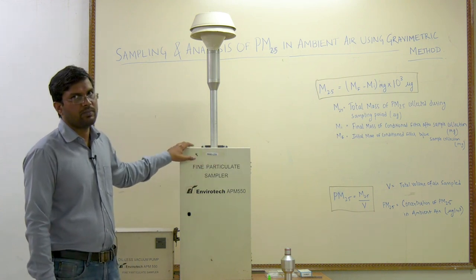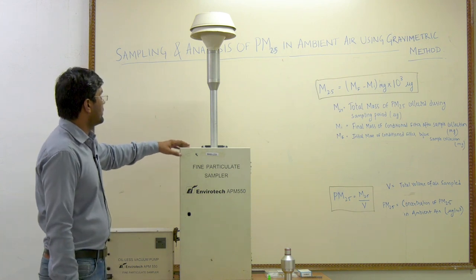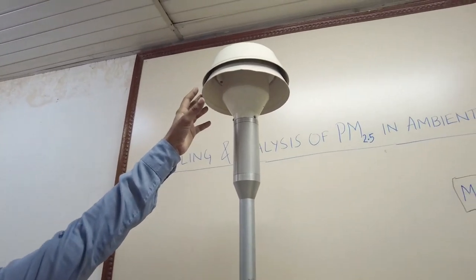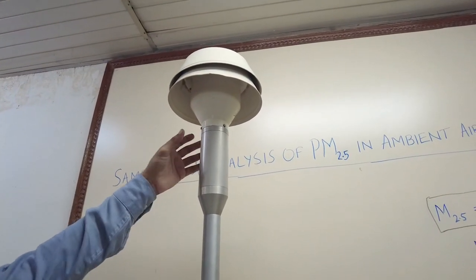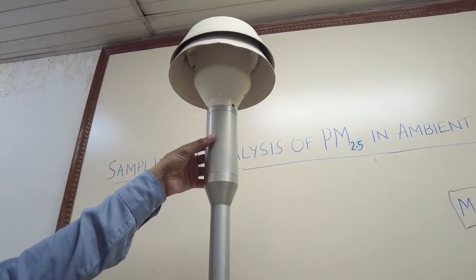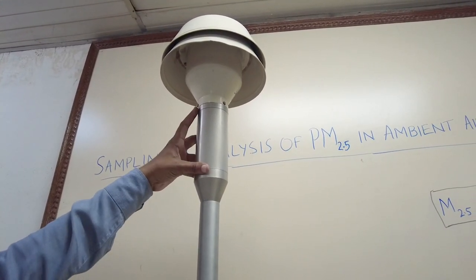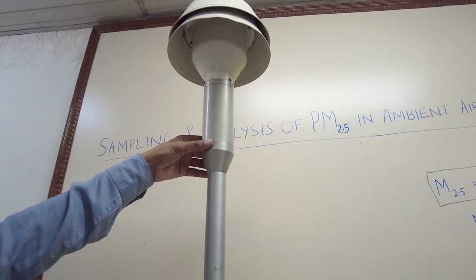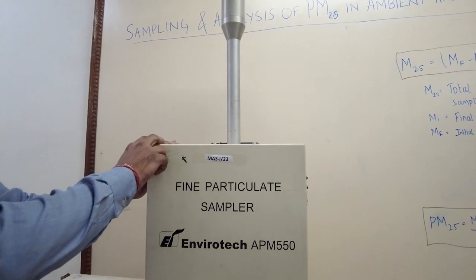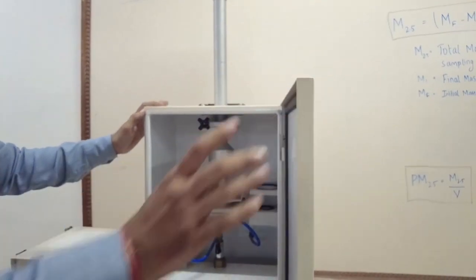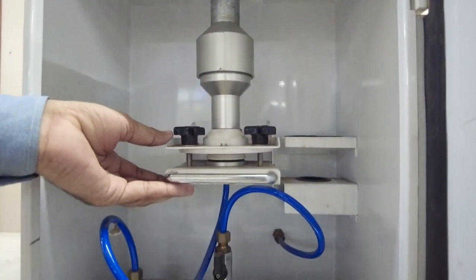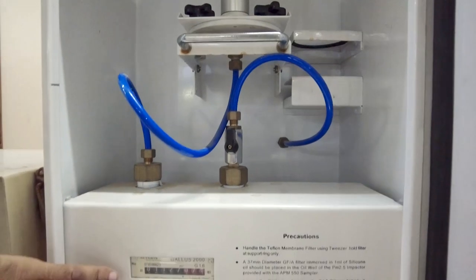I will explain the different components of the instrument. The upper part is called the inlet. After the inlet, this part is called the impactor — the PM 10 impactor tube — to segregate particles larger than 10 microns in size. Particles smaller than 10 microns will go through the air stream passing down through the down tube and into the housing of the APM 550 sampler. In the housing we have three major components: the WINS impactor assembly, the filter holder assembly, and the dry gas meter.